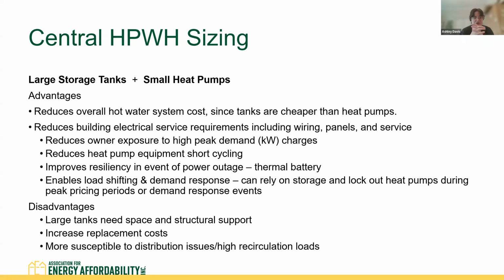Installing them this way also reduces owner exposure to high peak demand charges. It reduces short cycling, and it can also help improve resiliency in the event of a power outage, because really large storage tanks that are fully heated up can basically act as a thermal battery. This also enables load shifting and demand response because you can rely on the storage and lock out the heat pumps during those peak pricing periods or demand response events. So you size the storage tanks to cover the peak load, and then the heat pumps to be able to recover that storage capacity during the off-peak times.